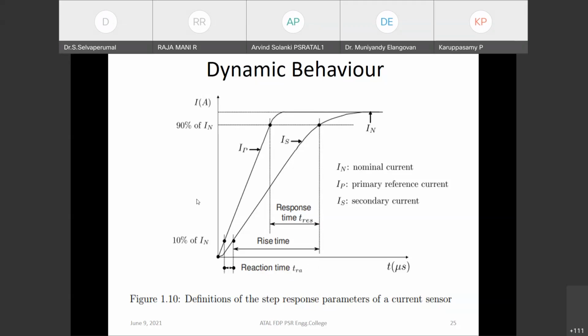A current sensor's response to a step current with controlled rate of change is characterized by the response time. It is the delay between the primary reference current reaching 90% of its final value and the sensor's output reaching 90% of its final value. During this measurement, the reference current shall behave as a step current. The typical value for closed loop is 1 microsecond and for open loop is 5 microseconds.